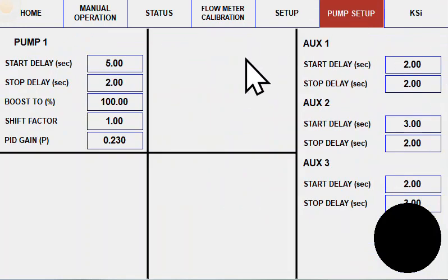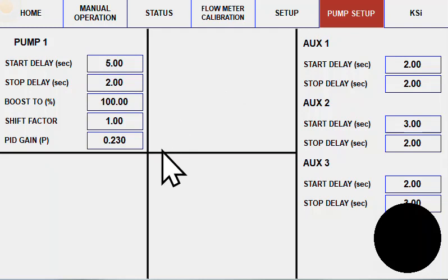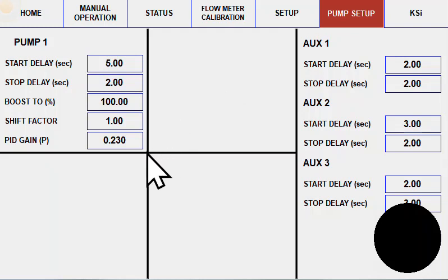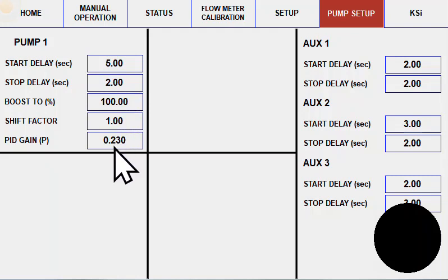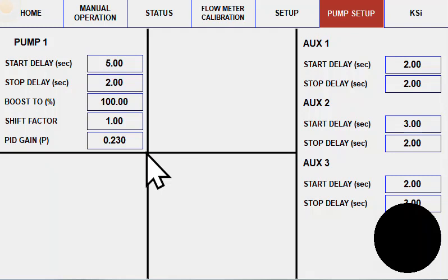The pump setup page has some additional pump parameters for up to four pumps or as many pumps as you have installed on the KSI system. It's got settings for start and stop delay as well as some boost percentages and shift factors for your pump to ensure and give the flexibility to dial in accuracy on a pump by pump basis.